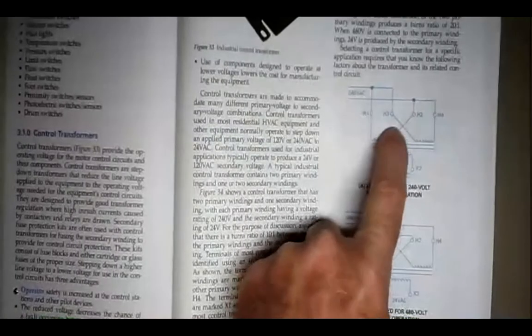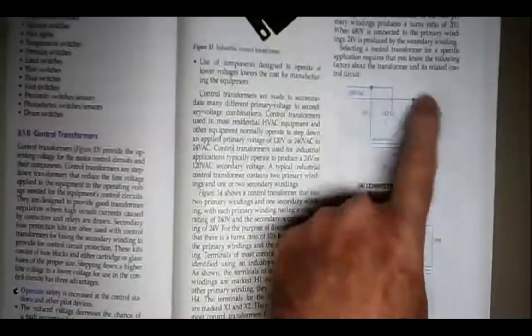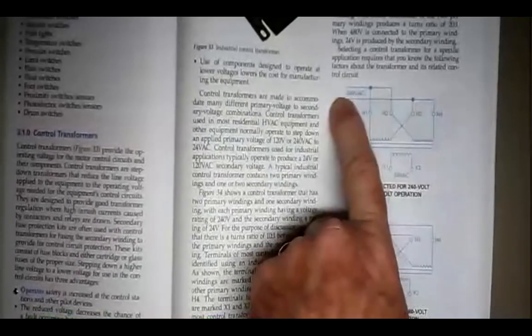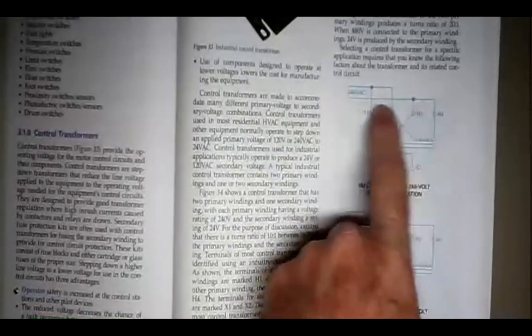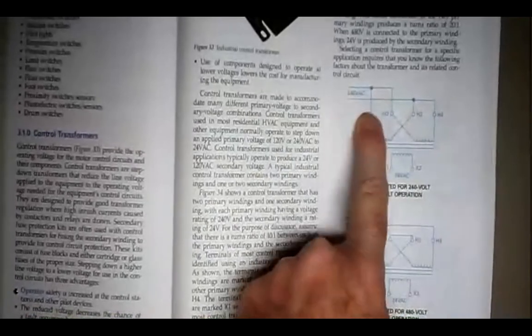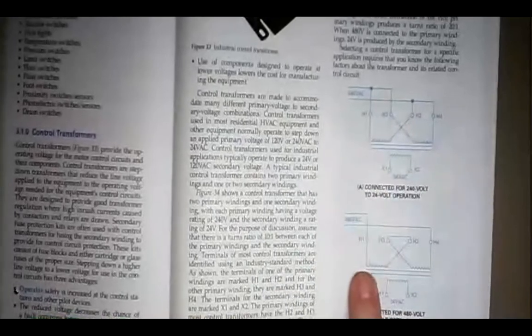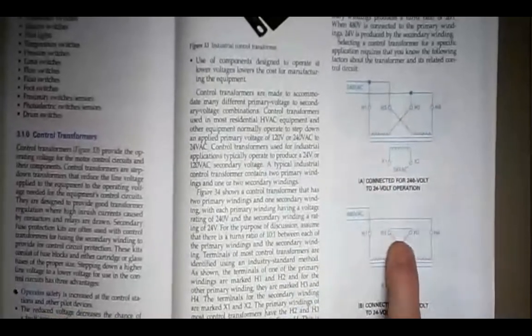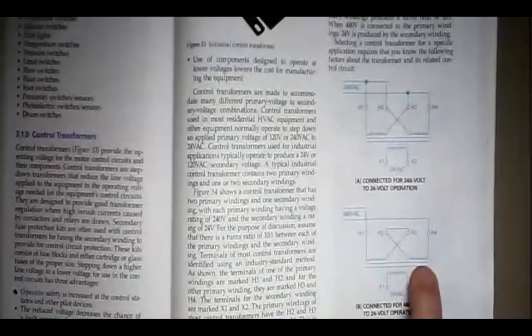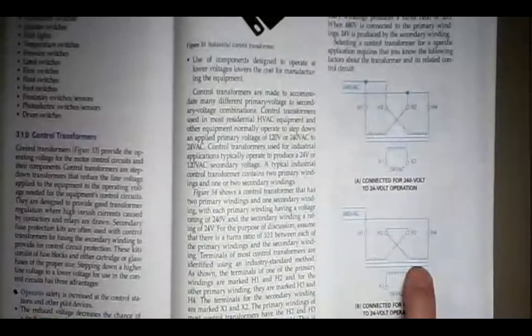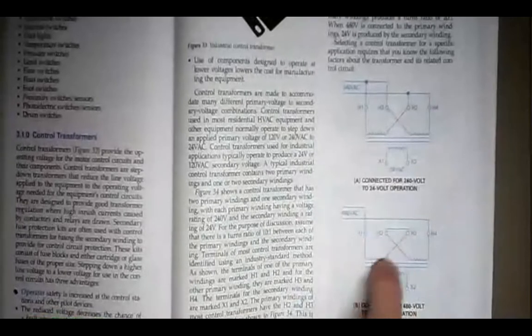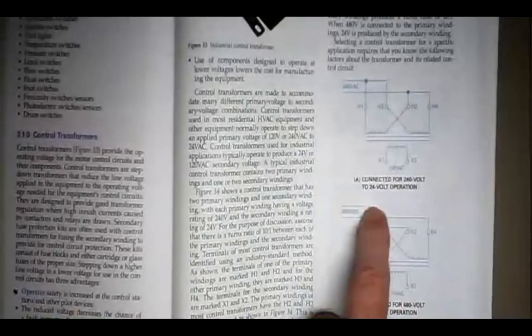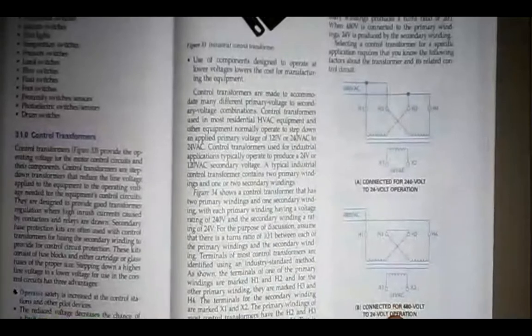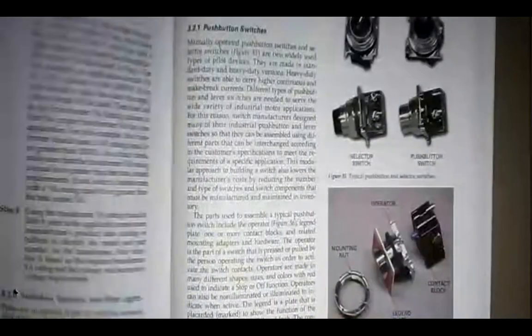And of course, because they've got 240 coming in, they're hooking these up in parallel. Series add voltage, parallel add current. So when they're hooked up in parallel, you can have 240 volts coming in, and each coil is getting 240 volts. When you have 480, you're going to hook them in series, and each coil will still only see 240 volts because they're in series. Series add voltage. So 240 plus 240, you've got a 480 volt input. You're still going to get your 24 volt output, your secondary on that transformer.